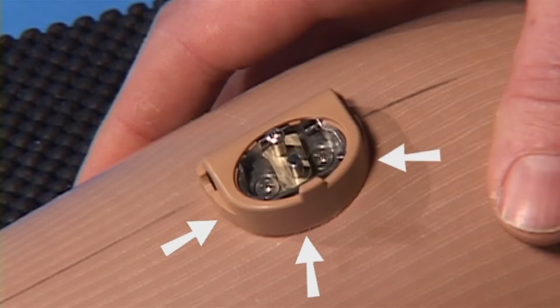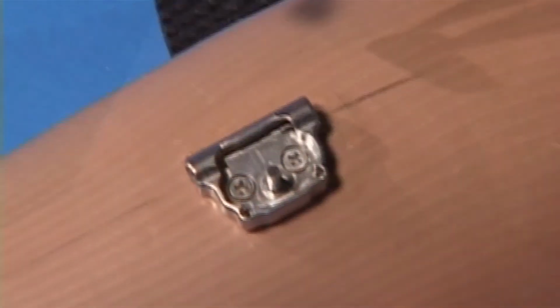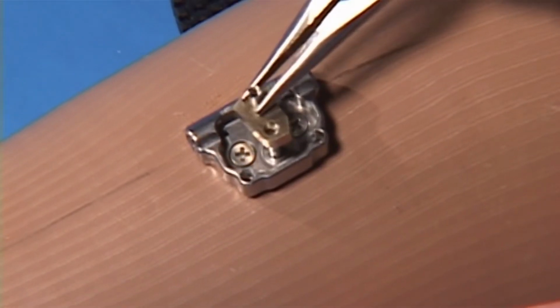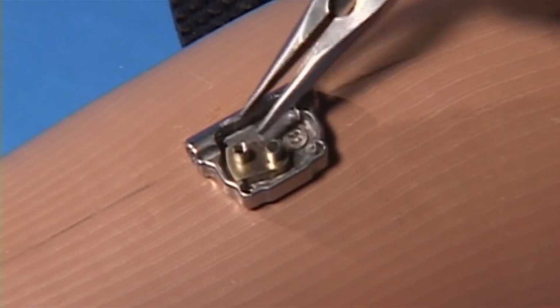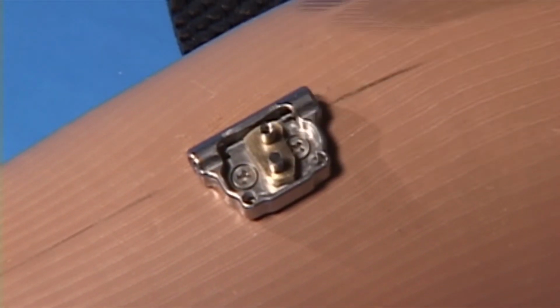The cover base should fit all around the perimeter snugly against the prosthesis, or with only a very small gap. If not, pry off the base and use a Dremel tool or similar rotary tool to adjust and reshape the cover base. Next, install the cam by placing a hole on the narrow or pointed end of the pin in the structural base. The threaded cam pin should face away from the structural base. A light machine oil such as Tri-Flow can be used on the axle as a lubrication.